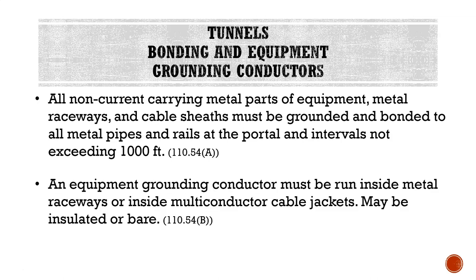An equipment grounding conductor must be run inside metal raceways or inside multi-conductor cable jackets, and that equipment grounding conductor may be insulated or bare. As we'll learn in module two, metallic raceway and some multi-conductor cable sheaths can act as an equipment grounding conductor — however when installed in a tunnel, they cannot. We have to run an additional equipment grounding conductor within them.